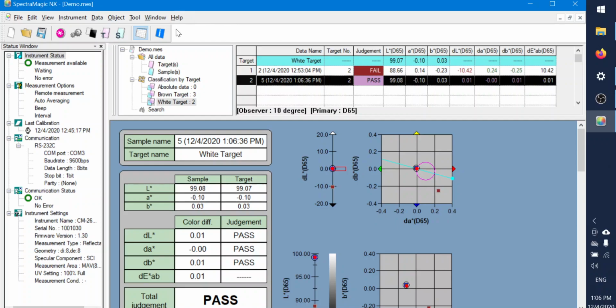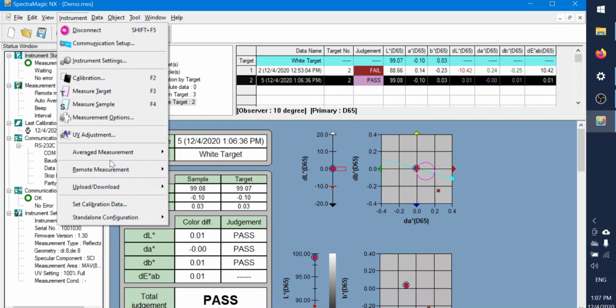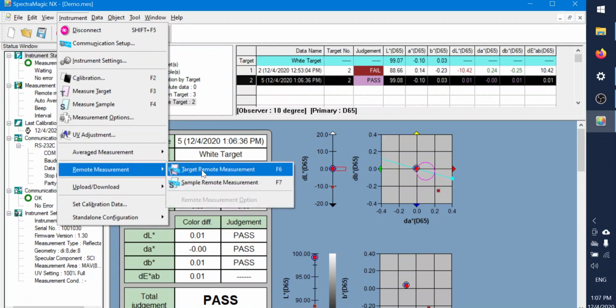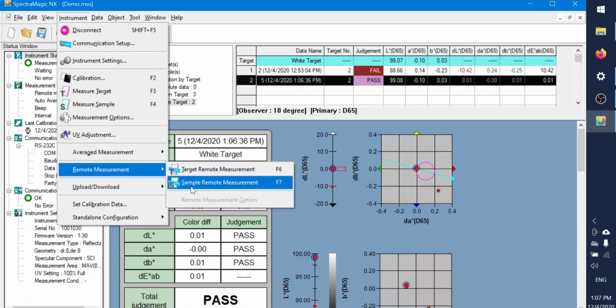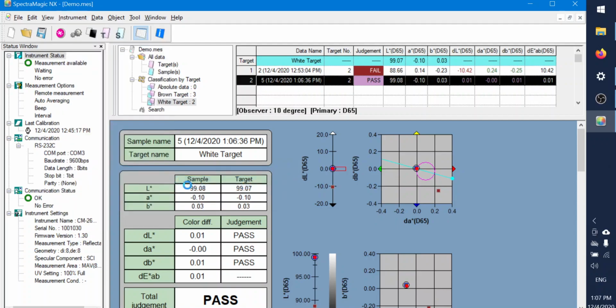There would be also a feature that allows you to click the measure button on the instrument to trigger measurements. So if you were to try to press the measurement button on the equipment, there will be no response to the PC. So in order to do so, you have to notice that the word remote measurement here has to be selected. Currently there is no selection of remote measurement, so we will go to instrument, remote measurement, and you could choose whether the remote measurement only does target measurement or sample measurement. I would prefer it to be selected for sample measurement. So I click on sample measurement, and you will see here it's selected. There is a tick beside sample remote measurement.